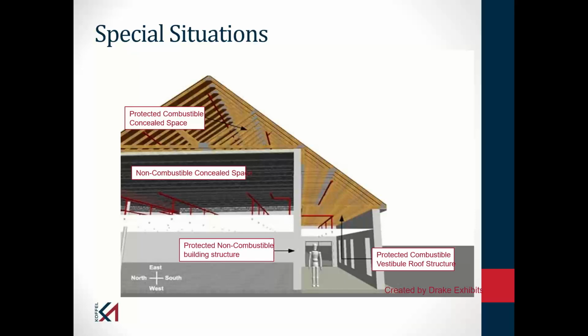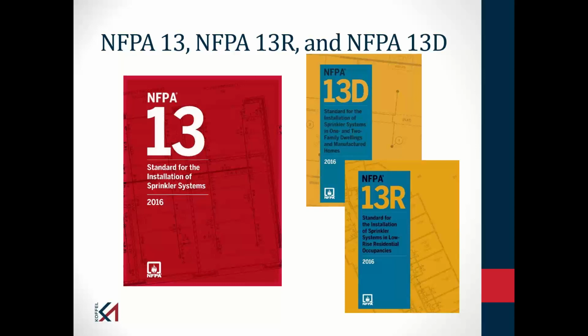Now, when I have combustible construction, the answer to that question is far more challenging, because there are some concealed combustible spaces that I need not have sprinklers in, according to NFPA 13. There are others that, to meet the requirements of NFPA 13, we would need to provide sprinklers in. And again, it would probably take about 30, 40 minutes just to go through those requirements related to combustible concealed spaces. If I discount the 2019 edition of NFPA 13, and I go to the ones I mentioned earlier, 2013, 2016, you'll find these provisions in 8.15 of the standard. Now, one of the differences between NFPA 13 and NFPA 13R and NFPA 13D is, in fact, those concealed combustible spaces.